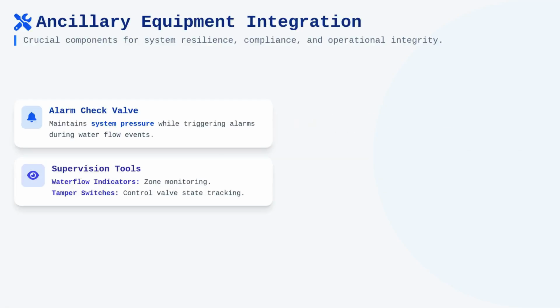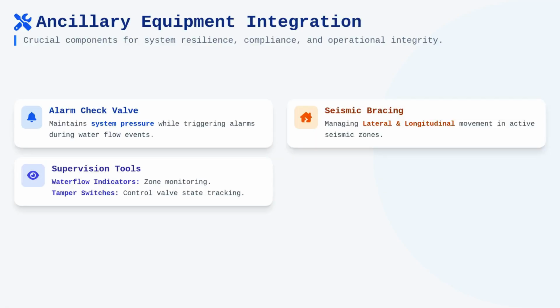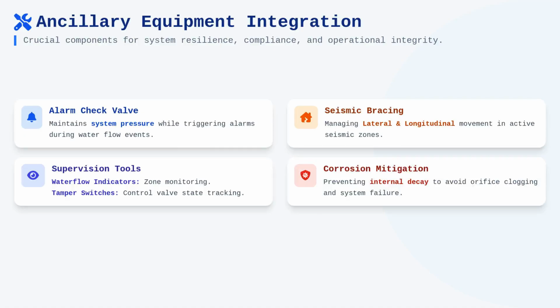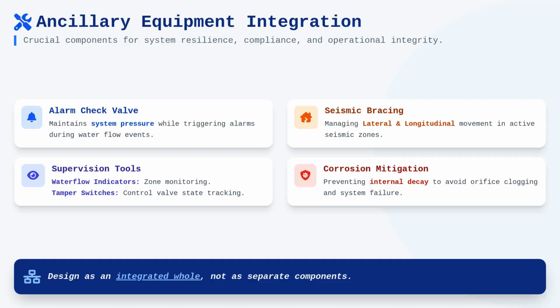the system state. In seismically active areas, bracing requirements become a primary design constraint, forcing us to account for lateral and longitudinal pipe movement. Furthermore, corrosion mitigation has become a major focus, as internal pipe decay can clog small orifices and ruin the effectiveness of the entire system. You must consider these factors as an integrated whole rather than treating them as separate components to design a resilient and compliant system.